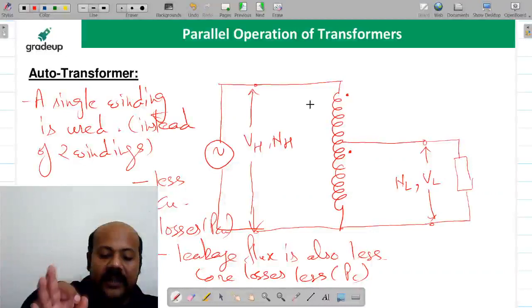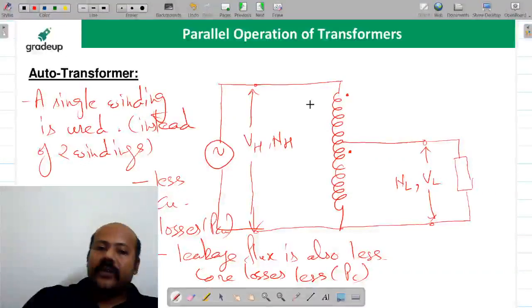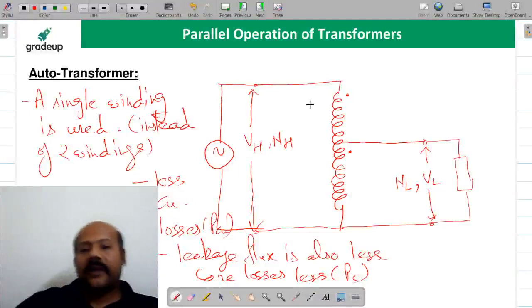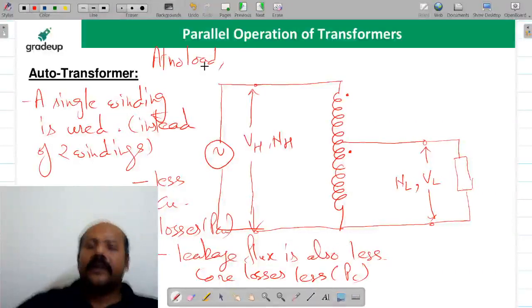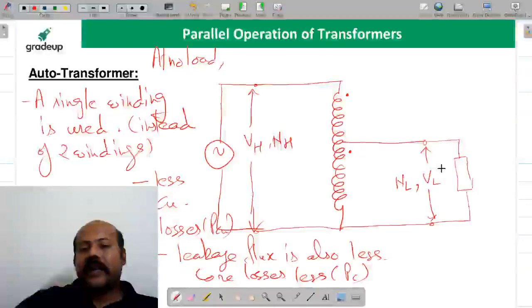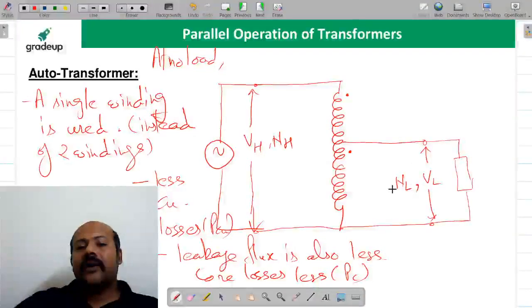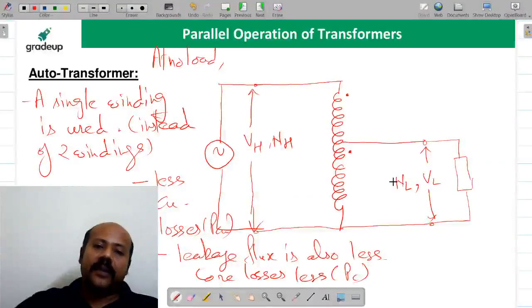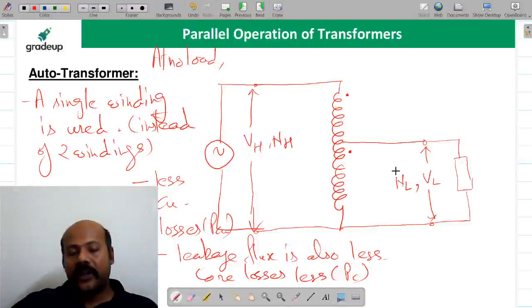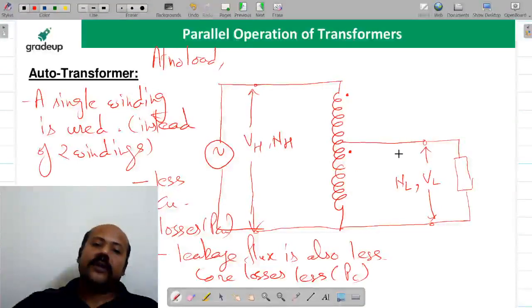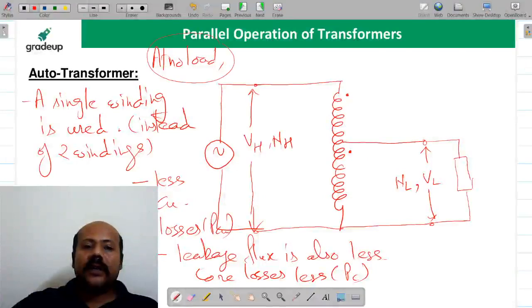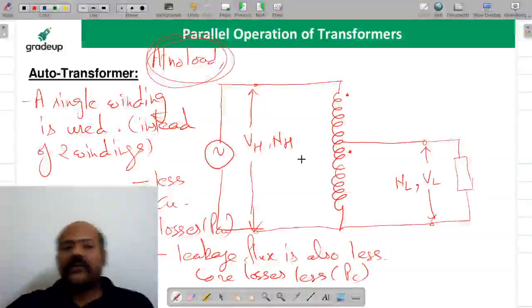Now Prashantni is saying that we are going to use less insulation. Please understand this problem: if you are using this type of autotransformer at no load condition, there is a possibility of very high voltage occurring on the low voltage terminal, and that may damage the insulation or the nearby personnel.